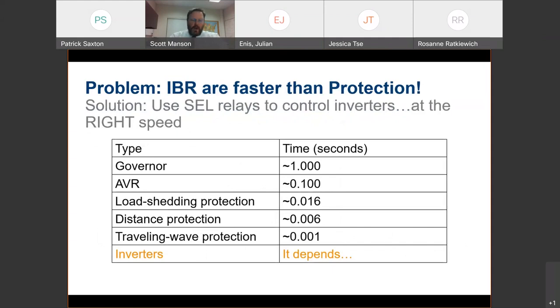Okay. Here's an interesting phenomenon. Inverters are now faster than many protective relays. They have a silicon carbide inverter system. They modulate at 40 kilohertz, 40,000 decisions a second. That is faster than most relays today. Not all, but most. To have a relay that operates at those speeds is very expensive, and that's a traveling wave relay. How do we protect a system where the very systems that are producing the current can trip off faster than the relay can even detect the current?